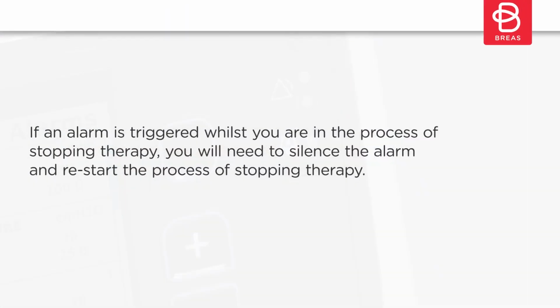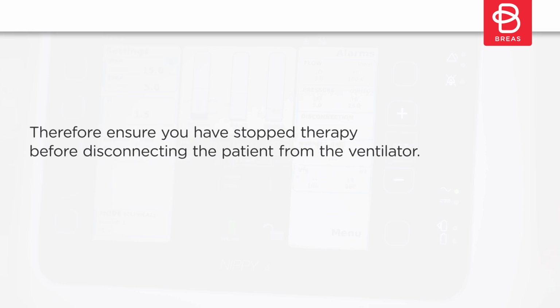If an alarm is triggered whilst you are in the process of stopping therapy, you will need to silence the alarm and restart the process of stopping therapy. Therefore, ensure you have stopped therapy before disconnecting the patient from the ventilator.